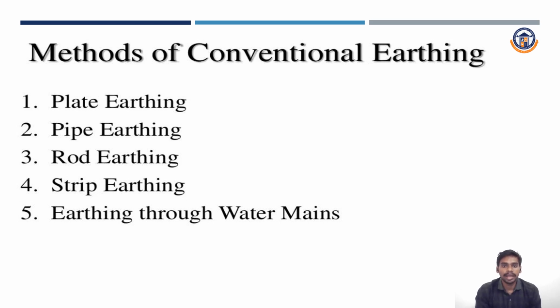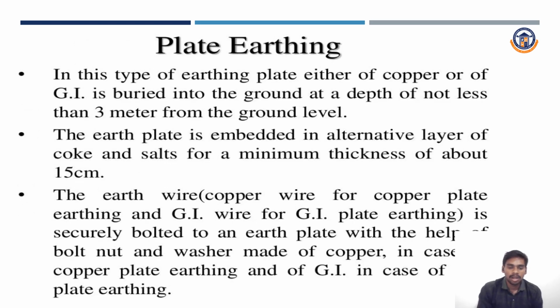These are the five types of conventional earthing: plate earthing, pipe earthing, rod earthing, strip earthing, and earthing through water mains. Now see the topic of plate earthing. In this type of earthing, a plate of either copper or galvanized iron is buried in the ground at a depth of not less than 3 meters from the ground level. The earth plate is embedded in alternate layers of coke and salt with a minimum thickness of about 15 centimeters. The earth wire, a copper wire for copper plate earthing and a galvanized iron wire for galvanized iron plate earthing, is securely bolted to the earth plate with the help of a bolt, nut and washer made of copper in the case of copper plate earthing and GI in the case of GI plate earthing.